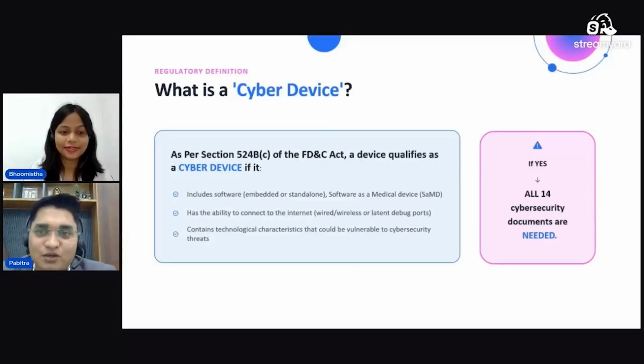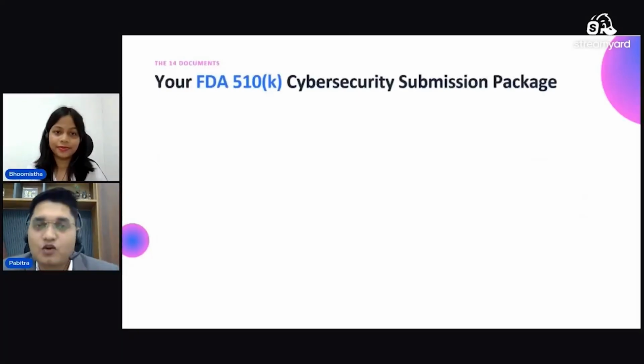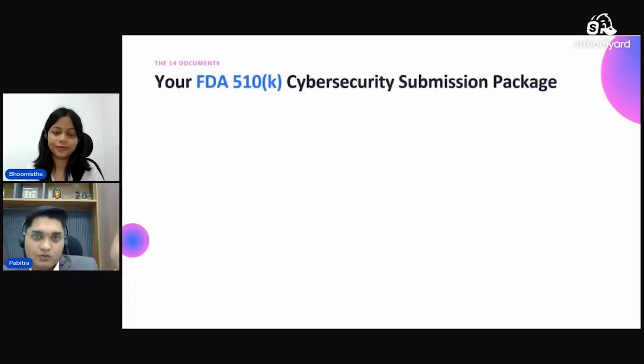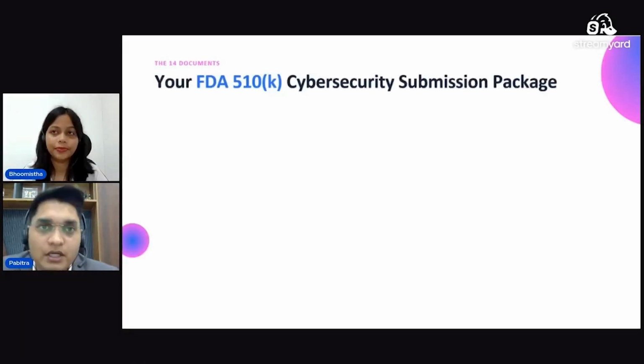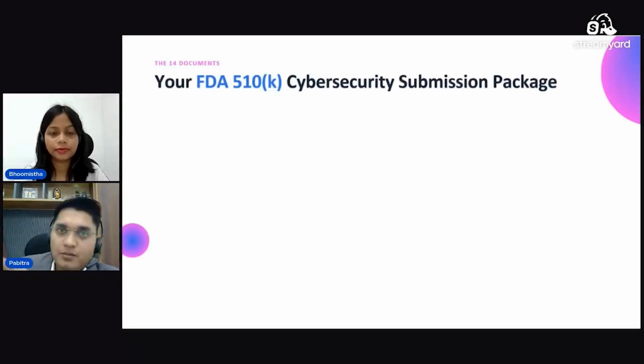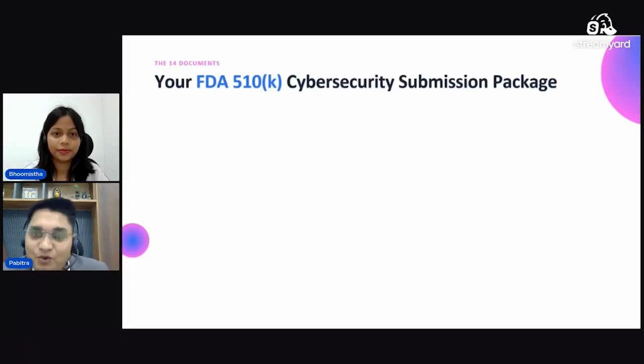Okay. So we'll move ahead with the 14 documents that are needed in the FDA 510(k). We have listed the 14 documents as a series, covering the steps or actions we have to take. We created these 14 documents according to the FDA documentation plan and our experience: our clients got approved with these documents. That's why we listed them.